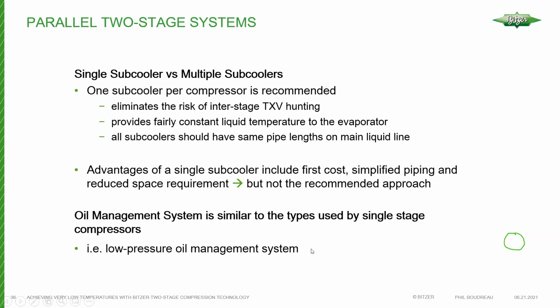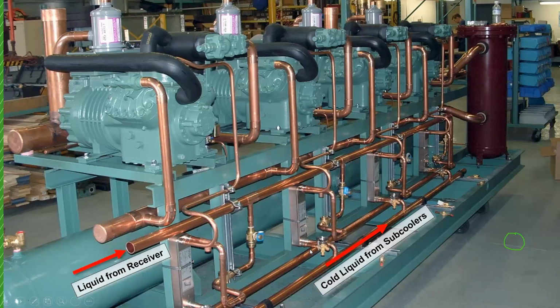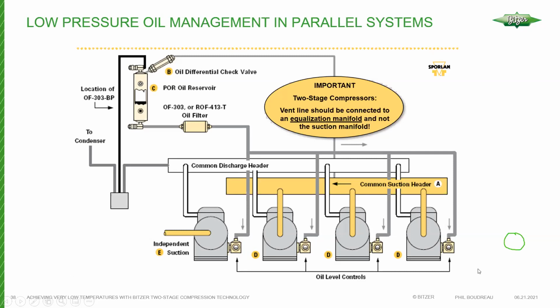Of course, the oil management system is going to be similar to any oil management system for single stage compressors, with a slight difference, which I'll show you in a moment. This is a picture of a rack that was built by BITZER Montreal several years ago. It shows the paths through each subcooler. You can see there are 1, 2, 3, 4 subcoolers here, one for each compressor. The liquid comes in from the receiver, takes a short path to the first subcooler, and then leaving the subcooler, it has this long path, where it says cold liquid from subcoolers, to get to the other end of the rack. The opposite subcooler, on the other end of the rack, you would pipe so that the liquid from the receiver travels a long distance to get to that subcooler, and then a short distance leaving the subcooler. In general, we're just trying to equalize the flows.